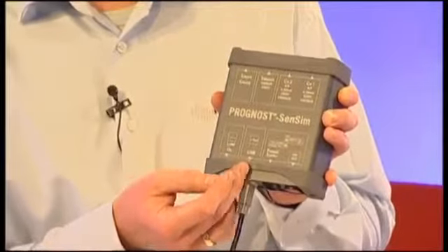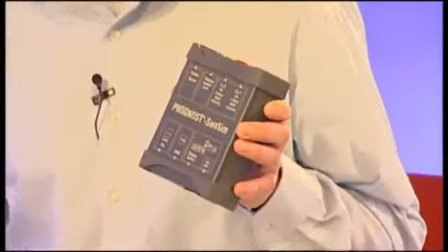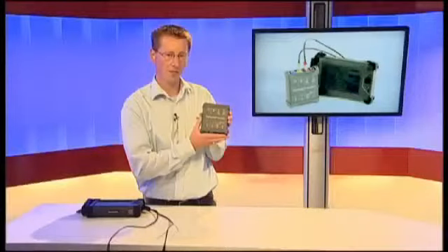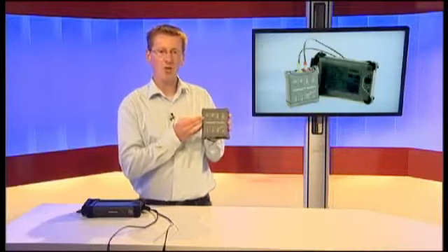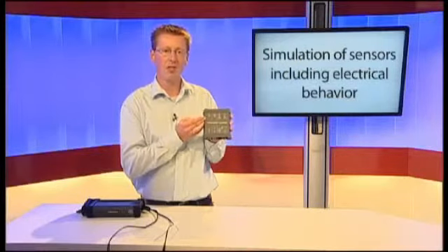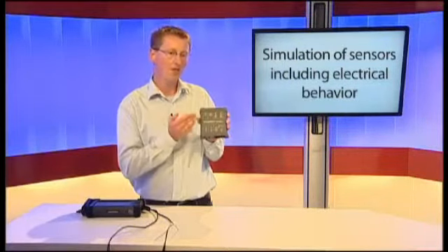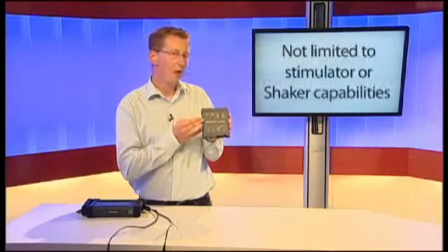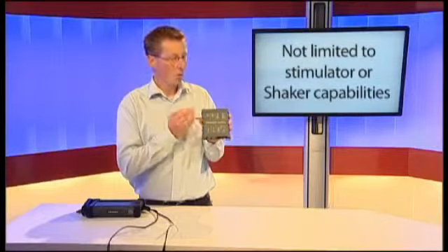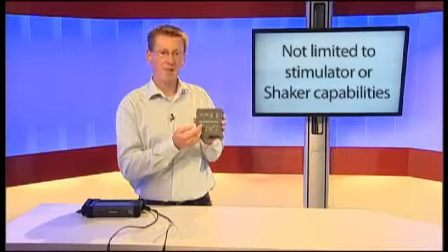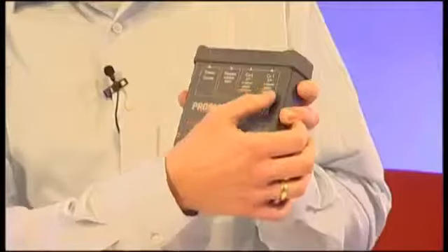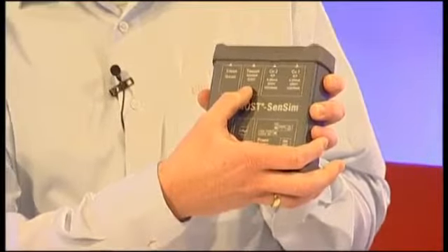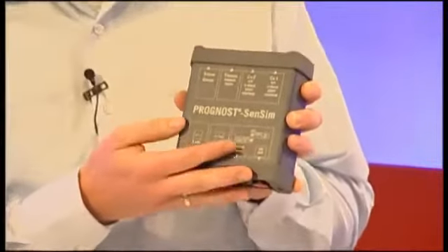To ensure user-friendliness, the generator can be disconnected after configuration and be used as a single piece of equipment for the test routine. With the PROGNOST SenSim, it is possible to simulate all types of sensors, including their electrical behavior. That means you can simulate the full sensor range and are not limited to your stimulator or shaker capabilities. Furthermore, with this device, it is possible to simulate all different types of dynamic signals fully phased to a given trigger signal. So let's talk about the simulated sensors that we offer.